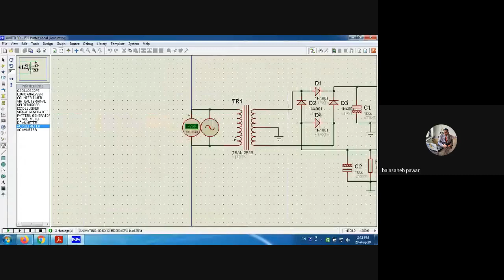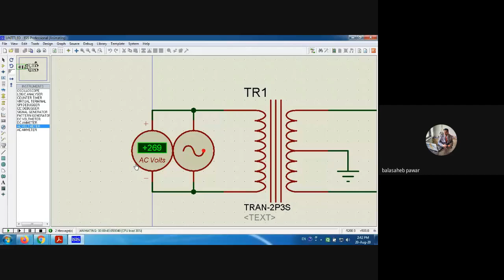That is 230 volt RMS. So from 200 to 250, you have to change the input supply voltage on this alternator, and verify it using an AC voltmeter across the alternator. That means your readings should be like 200 volt input RMS, 220, 230, 240, and 250. Note down if there is any change on the output of this regulator or not.